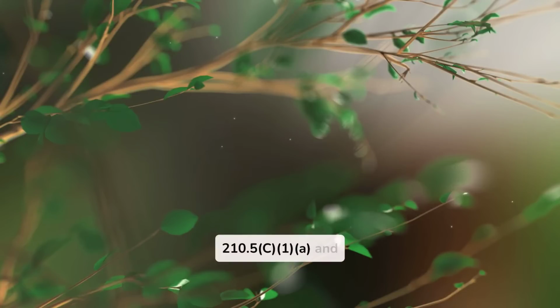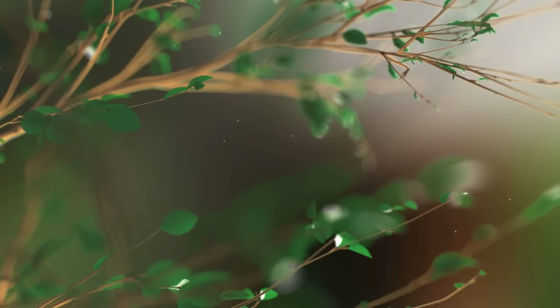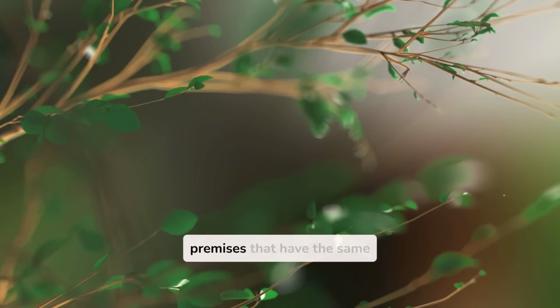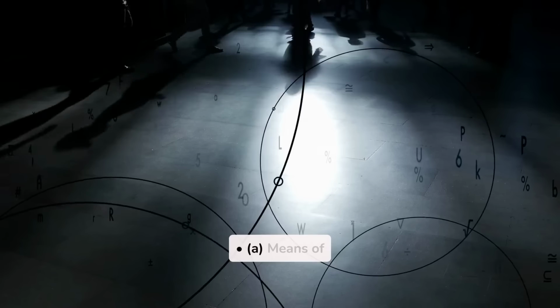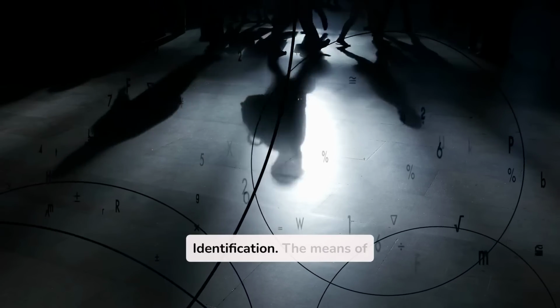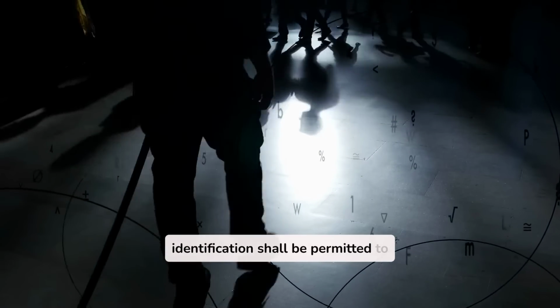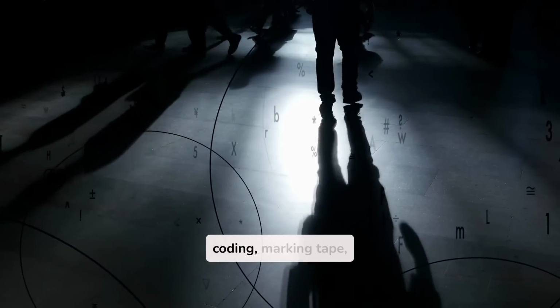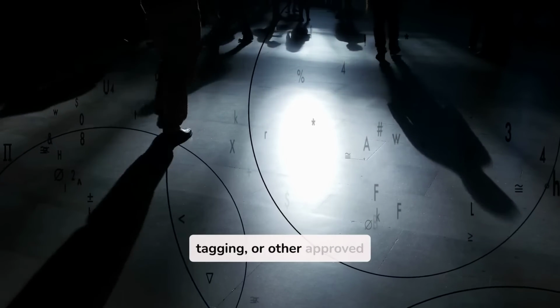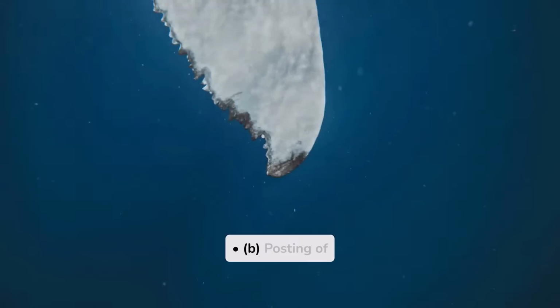Different systems within the same premises that have the same nominal voltage shall be permitted to use the same identification. A. Means of identification. The means of identification shall be permitted to be by separate color coding, marking tape, tagging, or other approved means.